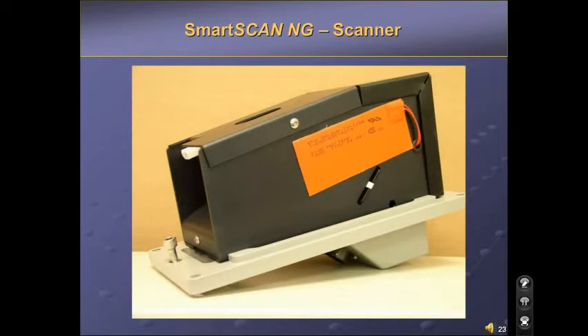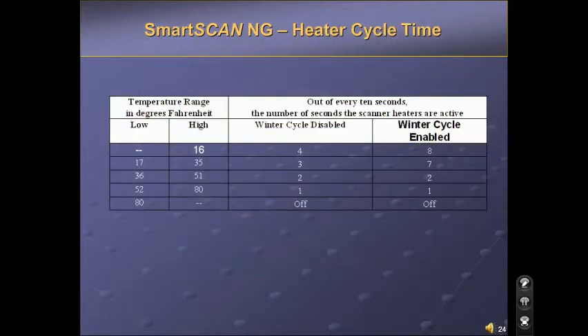This is the main body of the scanner. The heaters are controlled by the processor in the NG system. Its primary purpose is to keep the inside of the scanner dry and help melt snow in the winter. The heaters are set up on a cycle time. This table shows the length of time the heaters will be on with reference to ambient temperature readings.